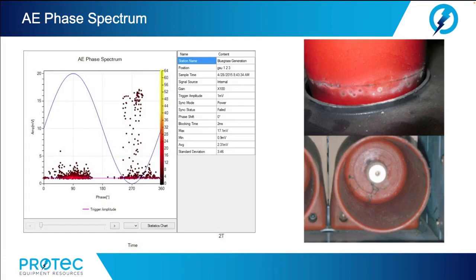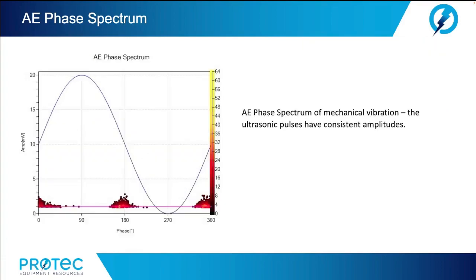AE phase spectrum plots the phase angle versus amplitude. The image shows the AE phase spectrum of a surface tracking partial discharge activity. The pulses have varying amplitudes. The pulses are different on the negative and positive half cycles. This is the AE phase spectrum of mechanical vibrations. The ultrasonic pulses have consistent amplitudes. The signals are the exact same on the negative and the positive half cycles.